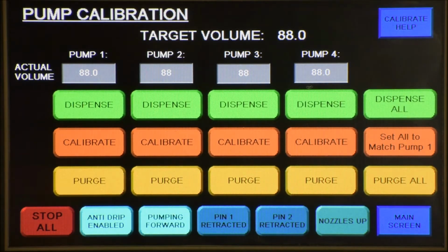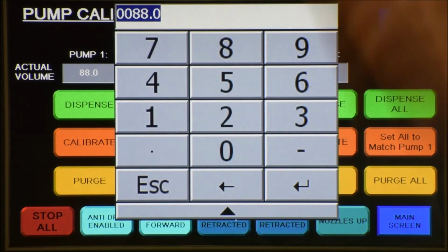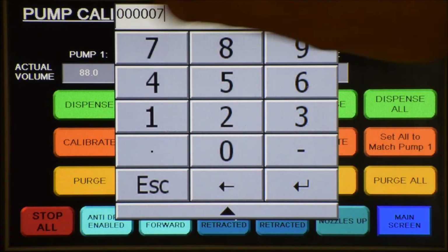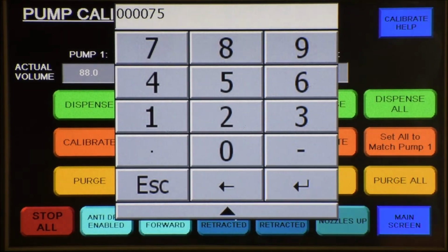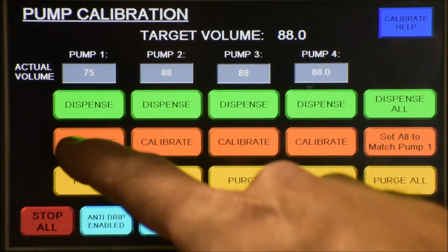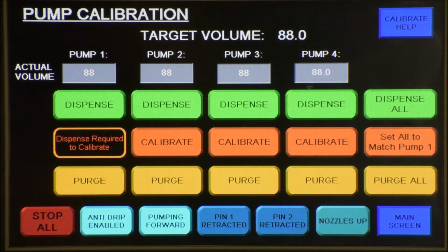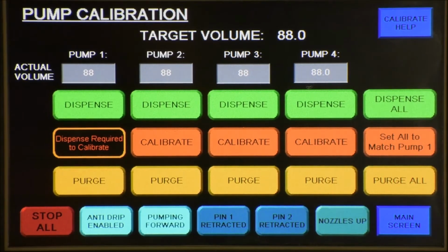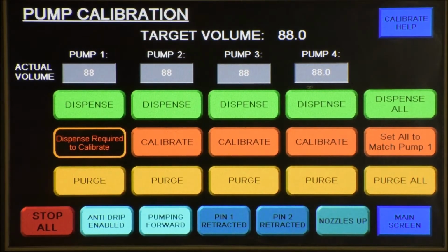Then you would go measure the volume that was dispensed, either in a graduated cylinder or using a scale if you know the density of your product. Let's say it was a little low. I'm shooting for 88 and I got 75. I'm just going to punch in 75, hit enter. Now I can hit calibrate. And what that's going to do is tell the system, hey, I only got 75, I was looking for 88. It's going to do the math to figure out how many more revolutions it needs to do on the motor to get to that volume. So you can see it changed that button that says dispense to required to calibrate.